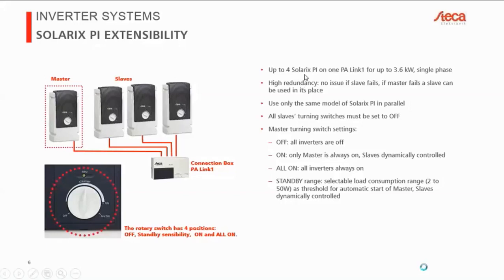So because we can connect up to 4 PI inverters on this PA Link 1, it means for 30 minutes, we have a higher power, and of course, we have a peak load that's even higher than that. Then we have a very high redundancy. Because we're using 4 devices here, it means that if one slave fails, for example, well, then nothing at all will happen. You will simply lose a quarter of the maximum power.